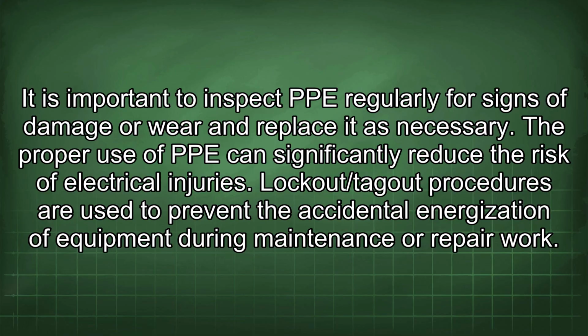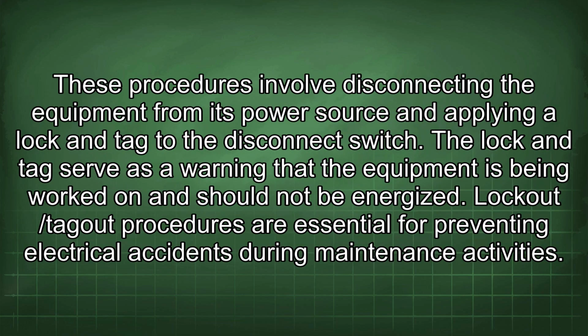Lockout/tagout procedures are used to prevent the accidental energization of equipment during maintenance or repair work. These procedures involve disconnecting the equipment from its power source and applying a lock and tag to the disconnect switch. The lock and tag serve as a warning that the equipment is being worked on and should not be energized. Lockout/tagout procedures are essential for preventing electrical accidents during maintenance activities.